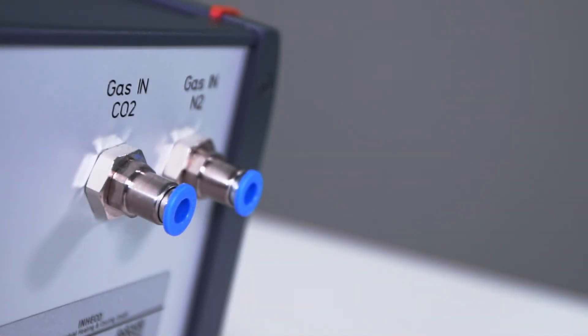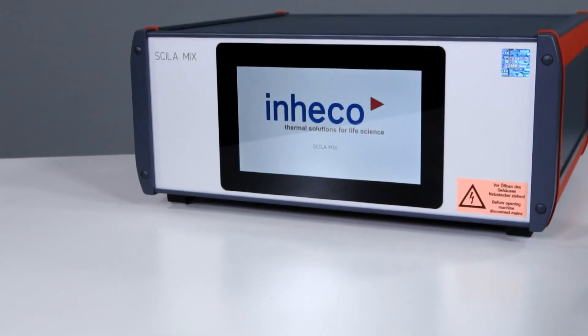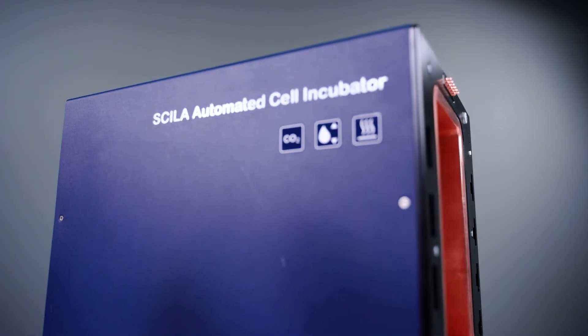In order to support gas concentration and humidity control, we provide a separate approved gas mixer, available as either a CO2 mixer or tri-gas variants. Our gas mixer is able to mix and provide a steady gas mixture to up to three separate SCILA devices.